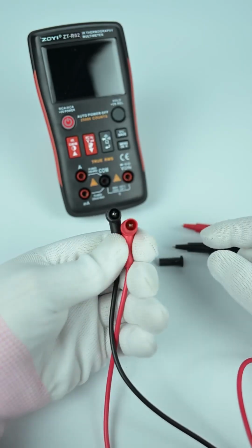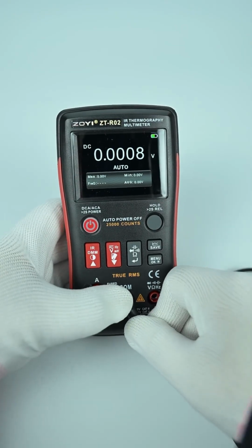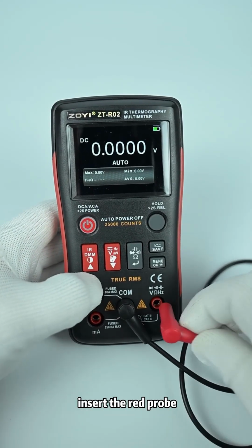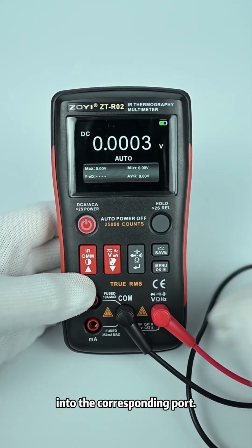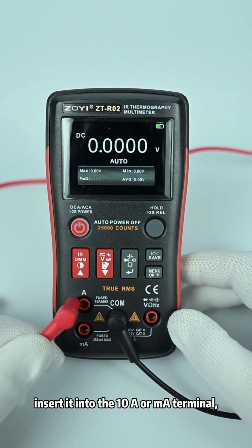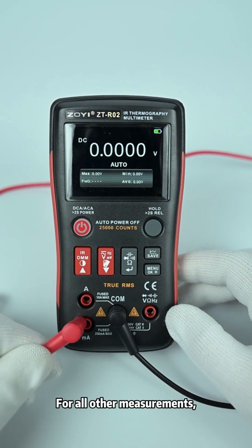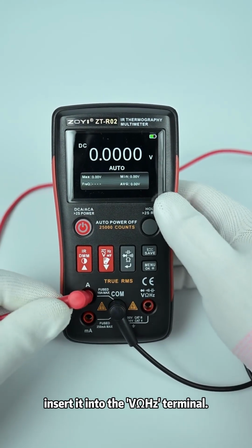Measurement operation procedure. Probe connection. Insert the black probe into the COM terminal, and depending on the type of measurement, insert the red probe into the corresponding port. For current measurement, insert it into the 10A or milliampere terminal. For all other measurements, insert it into the VΩHz terminal.